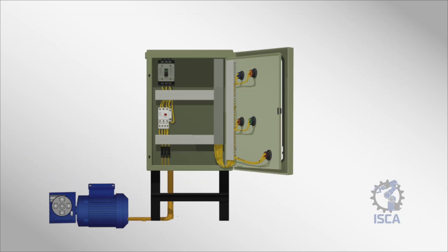An induction motor can be started using the simplest method known as a direct online DOL starter. This method involves directly connecting the motor to a three-phase power supply using a contactor and an overload relay to provide protection.